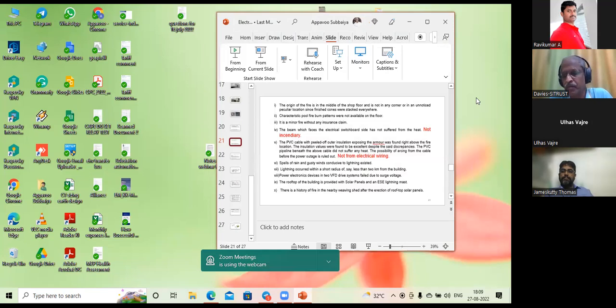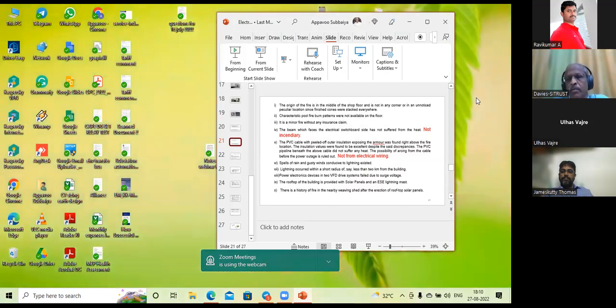Thank you, sir. Yes, these two things are vital to be known by every engineer, because we do not select the lightning arrester according to the coefficient of earthing, also your fault factor and the temporary overvoltage. A lot of parameters are needed to select a lightning arrester. Okay, we have selected a good lightning arrester. Then how to connect it? Even the connection: if you have selected a good lightning arrester and you fail in making a proper connection, then the system will fail. That's the first part.